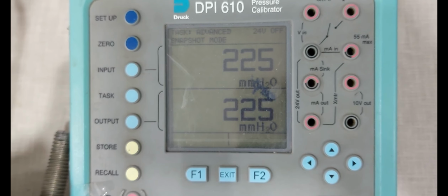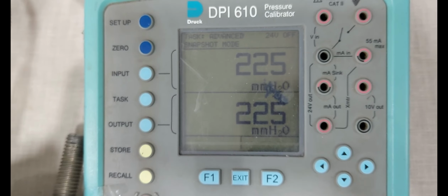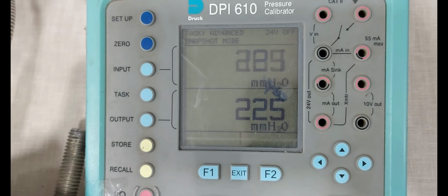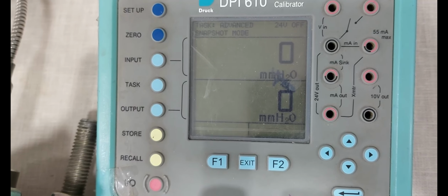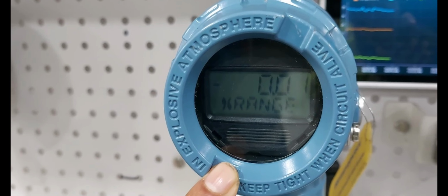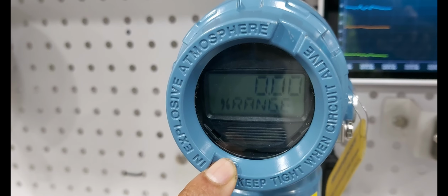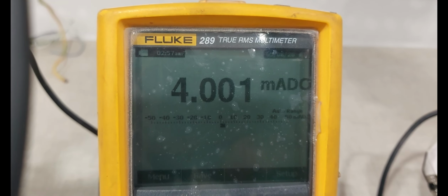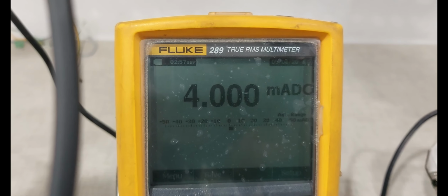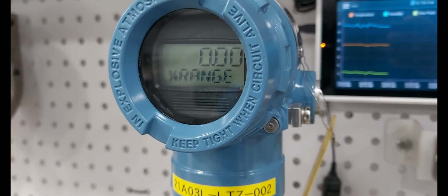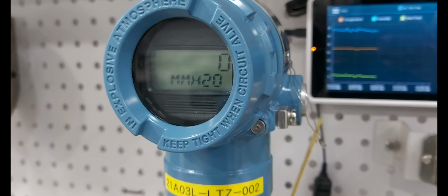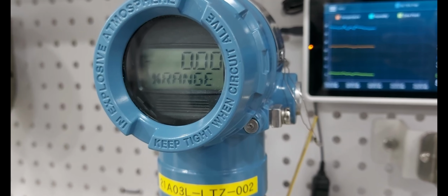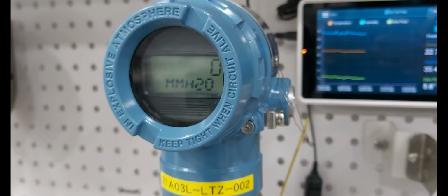Next we are releasing the pressure from the pressure calibrator. Now 0 is reached on the pressure calibrator. Transmitter display showing percentage value of 0 and the mmH2O also showing 0. Now output value 4 milliamps reached in the multimeter. Now transmitter calibration, verification, configuration, all are completed. This is a normal scenario for capillary type LT calibration and functional test.